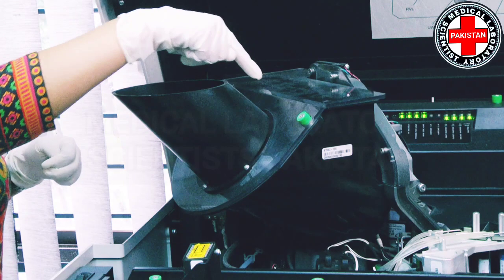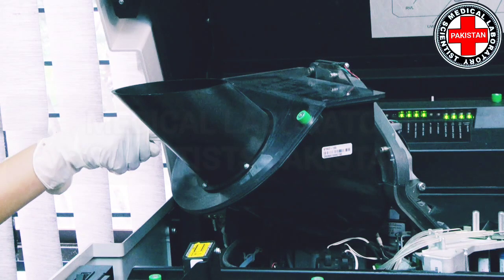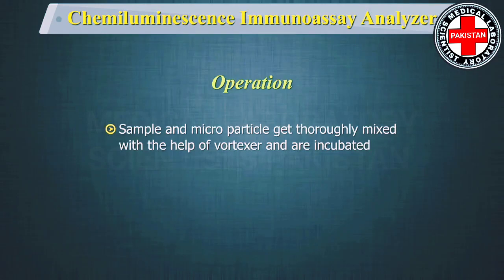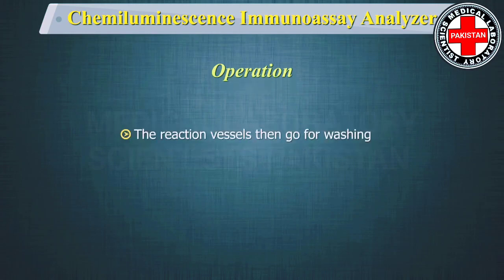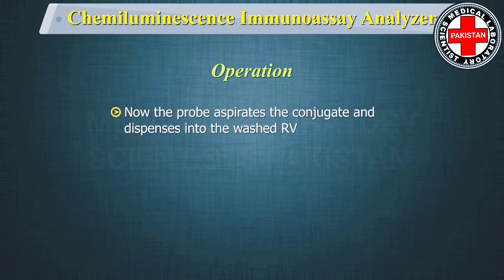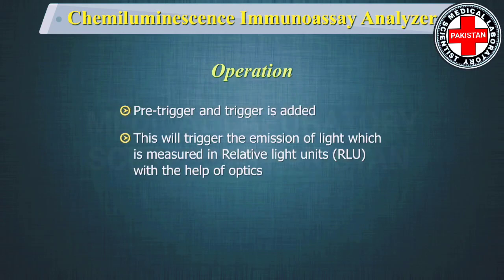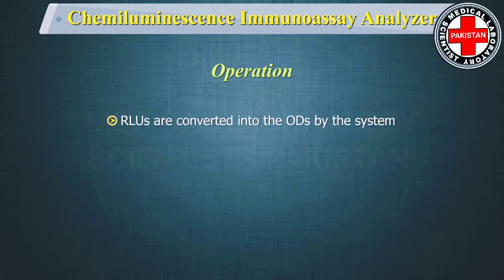The reaction vessel is picked by the picker arm and dropped into the process path. The probe picks the defined amount of sample and dispenses it into the reaction vessel, then aspirates the microparticle solution and dispenses it as well. Sample and microparticles are thoroughly mixed with the vortexer and incubated. The reaction vessels then go for washing, with the probe washed between each step. The conjugate is aspirated and dispensed into the washed reaction vessel, mixed, incubated, and washed again. Pre-trigger and trigger solution are added, triggering light emission measured in relative light units by the optics. RLUs are converted into optical densities by the system and the reading is given for the analyte.